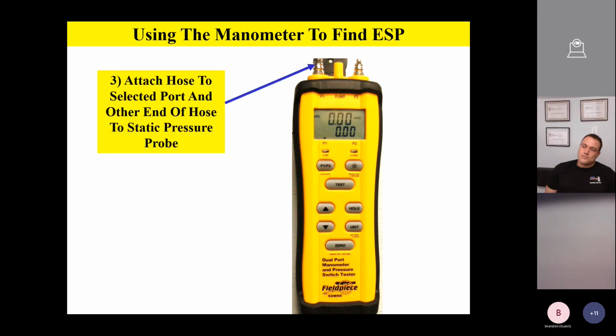The third thing we're going to do, we're going to make sure and attach our hose to the selected port, whether it's P1 or P2. And the other end of that hose is going to go to what we call a static pressure probe. Now, this is a special probe for taking static pressure. And so we'll be looking at that in just a moment or two as well.